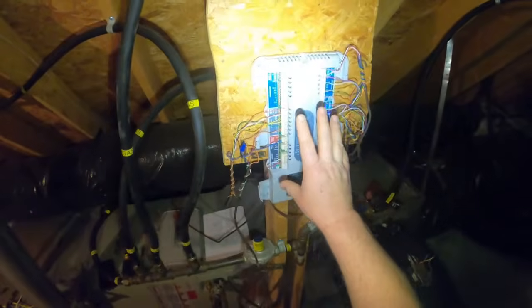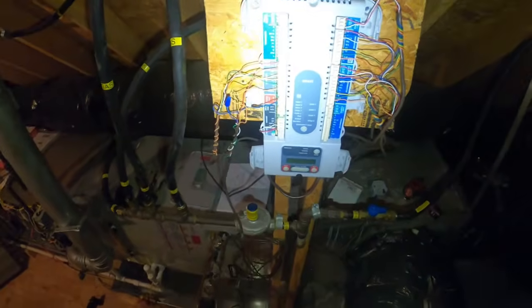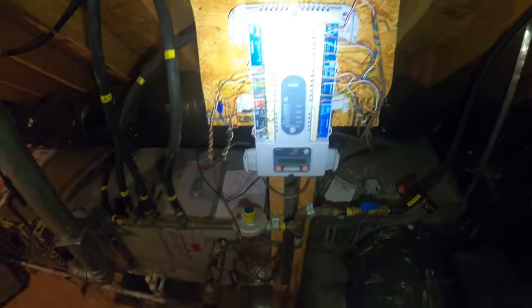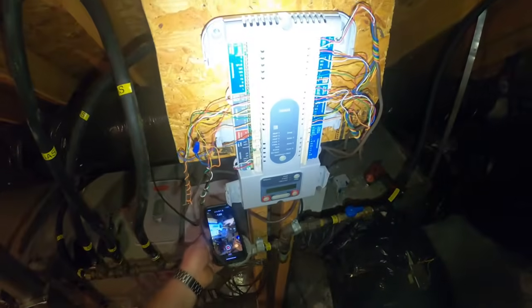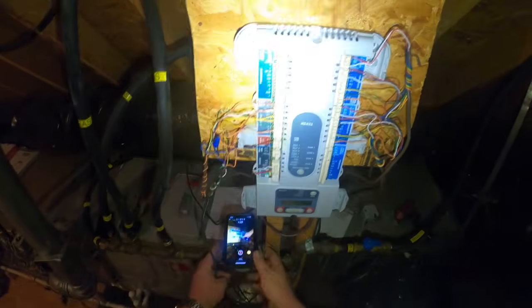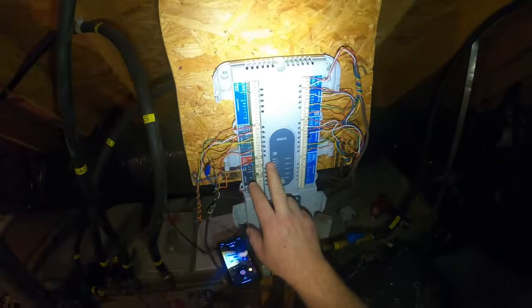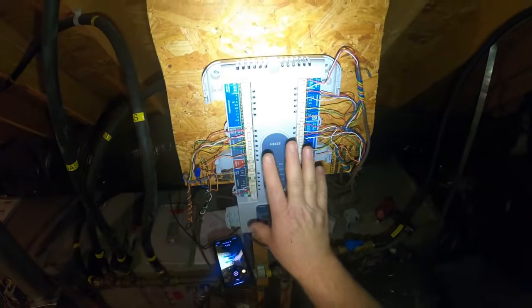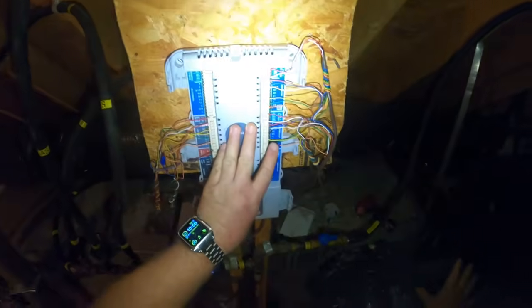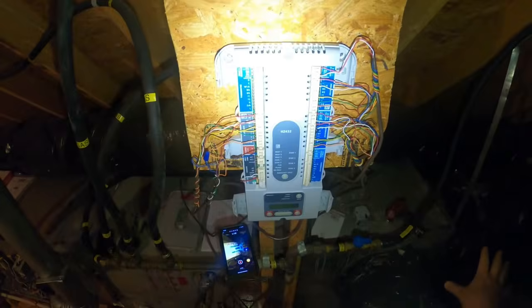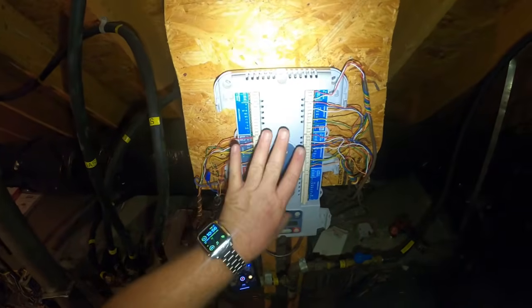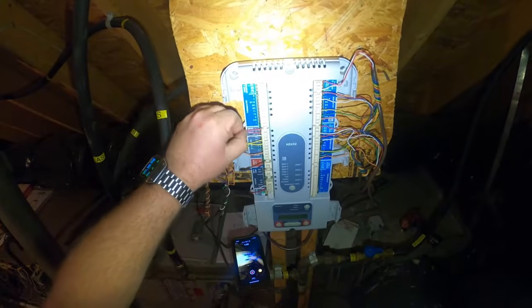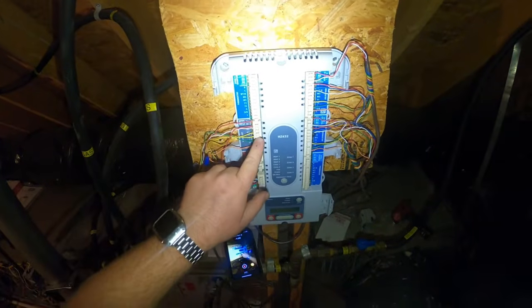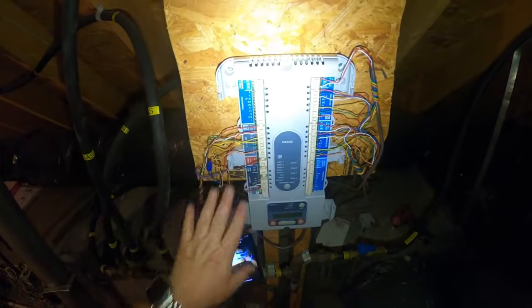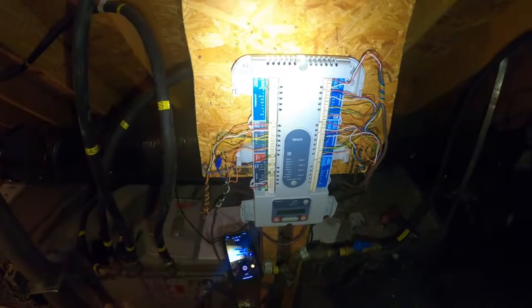You don't want to run the zoning control off of the equipment, especially a furnace transformer. If it's a small transformer, you're going to have an issue with coming over here. And I guess the easiest way to explain it is you run power to this zone board, you tie in a transformer. Now that transformer is going to power your zone board, it's going to power your thermostats, and it's also going to control the power on your damper motors when they open and close. At that point, this board just basically acts like a relay with the equipment, 24 volts, and relays it to your furnace, your outdoor unit, your reversing valve, your fan, whatever you're trying to do to control the system, and the equipment still runs off its transformer.